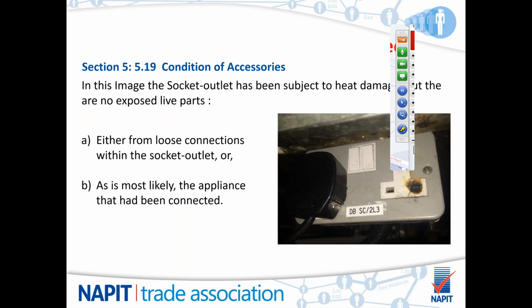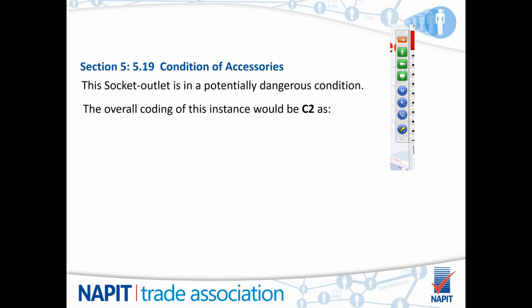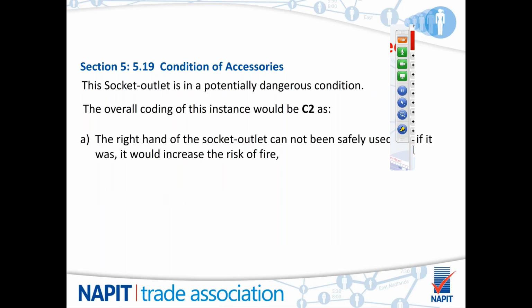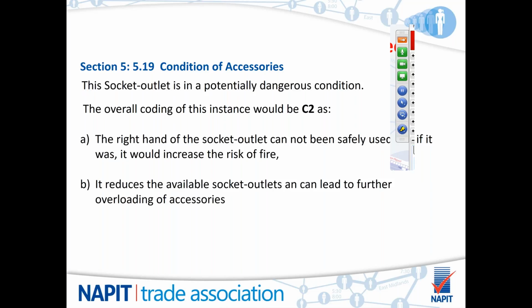Again, an overall code of C2. Touching the socket itself will probably not kill anybody. It is not immediately dangerous in that respect, but the right hand socket cannot be safely used. It is showing signs of thermal damage. Using it more and more, this is not going to get any better. It will only get worse. Using the only socket available on the left will mean it could be used with extension leads, extension cubes, meaning the overloading could be made even worse.